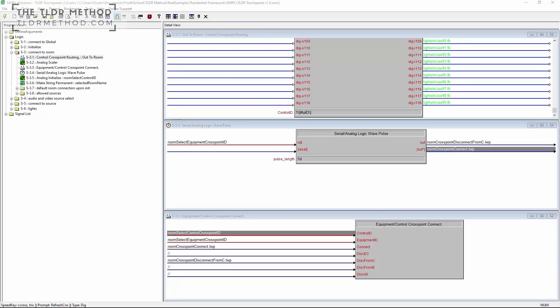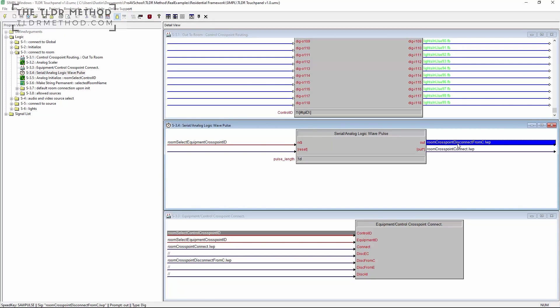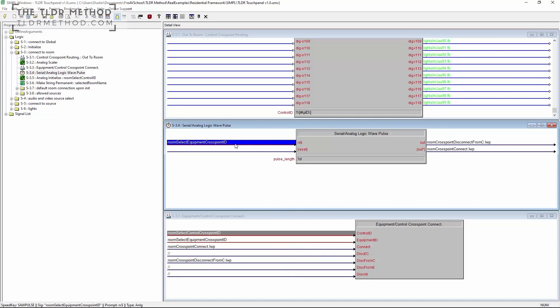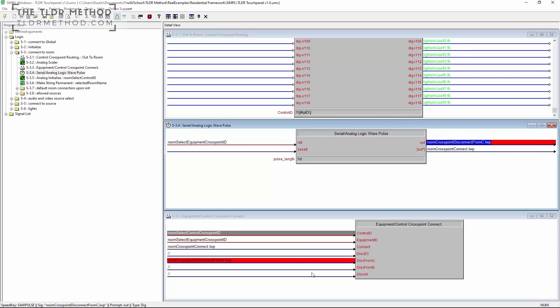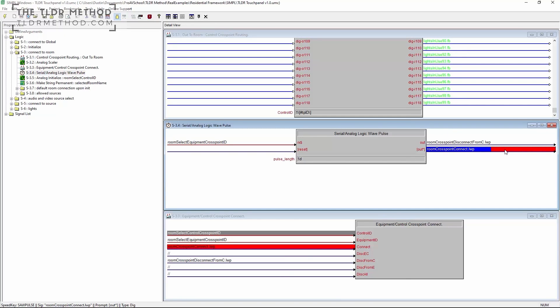In a typical system, you might have a control cross point connected to signals from a touch panel, and then an equipment cross point in a number of room logic locations. When you select a new room, the system would disconnect all equipment IDs from the control cross point and then connect it to the requested equipment ID. We can do this very cleanly and dynamically using a serial analog logic wave pulse — or speed key SAW pulse. The room select analog value drives the input. On the outputs, we use the regular output to drive the disconnect and the inverted out-star to drive the connect. This will wait for a change in the analog, immediately disconnect from the old equipment cross point, and then connect to the new equipment cross point. This connection happens fast, requiring only two logic waves.